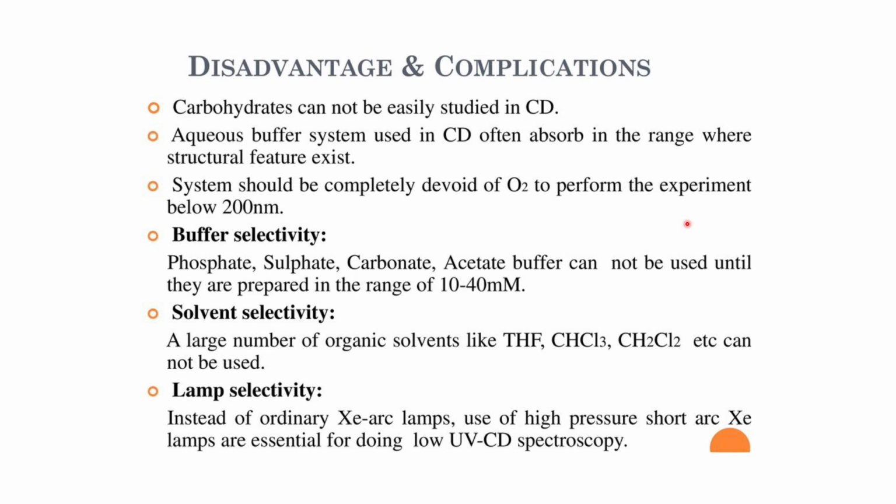And instead of ordinary xenon arc lamps, the use of high pressure short arc xenon lamps is essential for doing low UV CD spectroscopy.